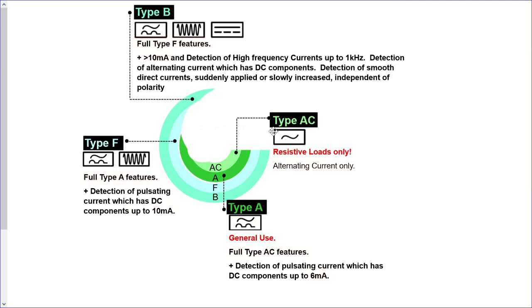Why? Well, when we look at the different types of RCDs, type AC RCDs, we should be using them only in installations where we have purely resistive loads. Okay, whereas now the general use RCD that we should be using is a type A RCD that allows up to 6 milliamps getting inserted back in through the toroidal core. If we used a type AC and we had these electronic components connected that are dumping the DC components back into the RCD, we would have reduced or extended tripping times. Okay, if we had a type AC RCD in front of these circuits.